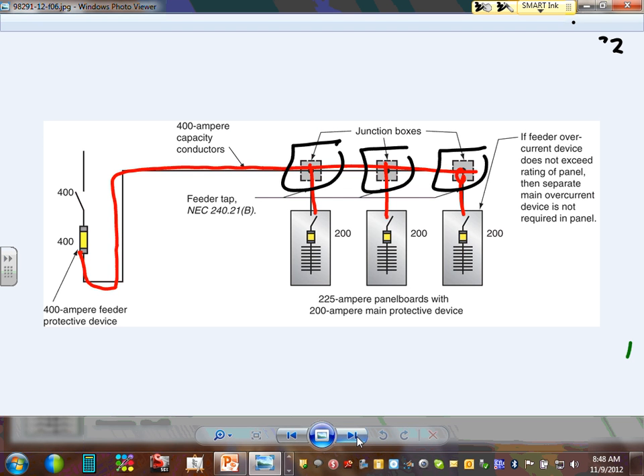I want you to remember, guys, when we size panels, the overcurrent protection device must be equal or less than the panel size. You guys remember that? So if this is a 200 amp panel, this is a 225 amp panel, can I put a 400 amp circuit breaker ahead of it? No. Can I put 200 amp ahead of it? Yes. For panels, there's the size of the copper inside it and the size of the circuit breaker ahead of it or in it. The size of the copper has to match the size of the overcurrent protection device or be more. Can you guys see that?